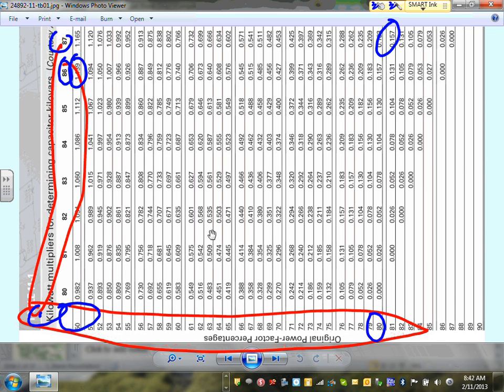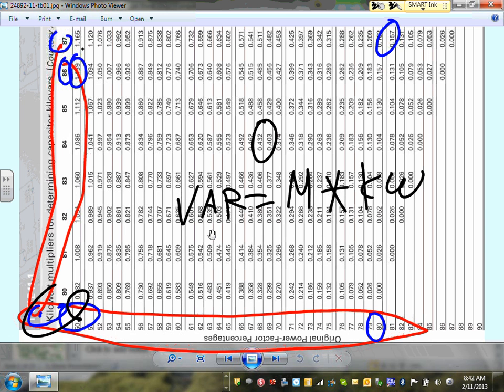But this is very, very important. To find the VAR, what they do is take that multiplier multiplied by the kW of your system. So you take any of these numbers based on what your original power factor is and what you want to correct to, and you multiply it by the kW, and it will give you the size of the capacitor that you need. Can you give a thumbs up on how this table works, guys? Because this is important for tomorrow. So if I want to correct my power factor from 50 into 89, I take this number that I came up with, and that will be my multiplier. And if the kW of my system was, say, 1,000 kW, then you multiply that number by 1,000, and that will get you how many VARs you need to correct in your system.